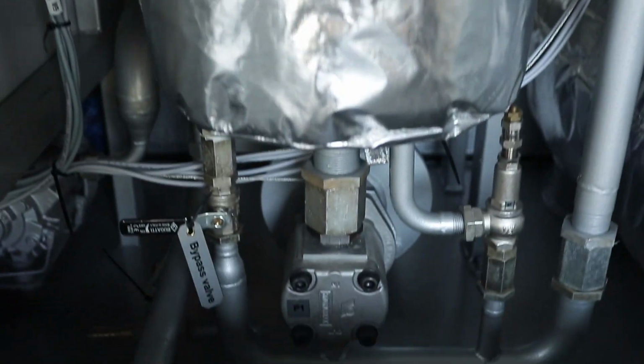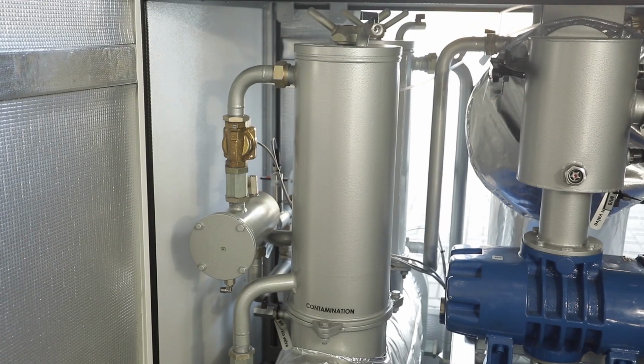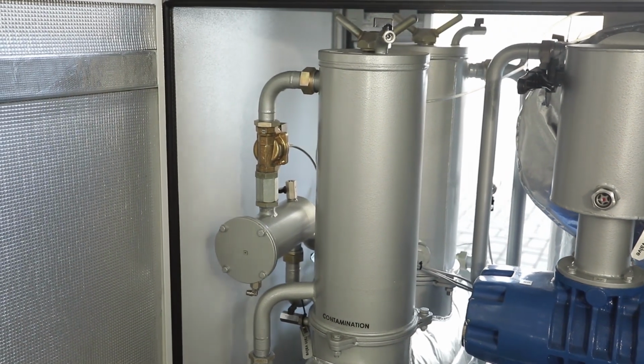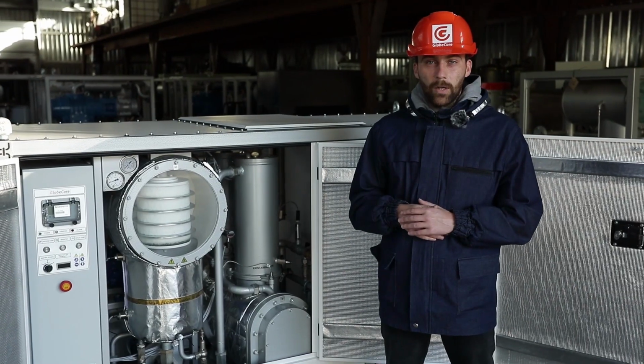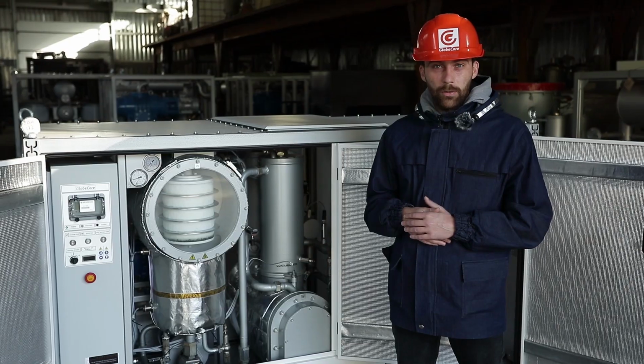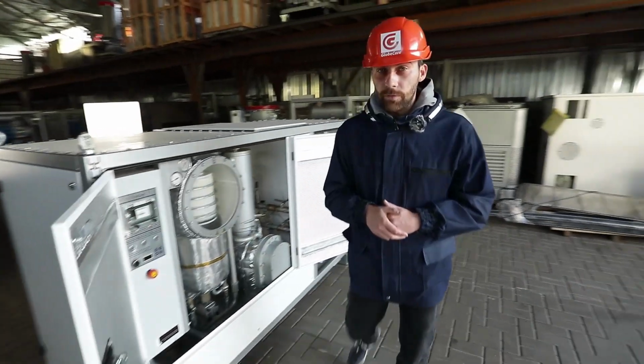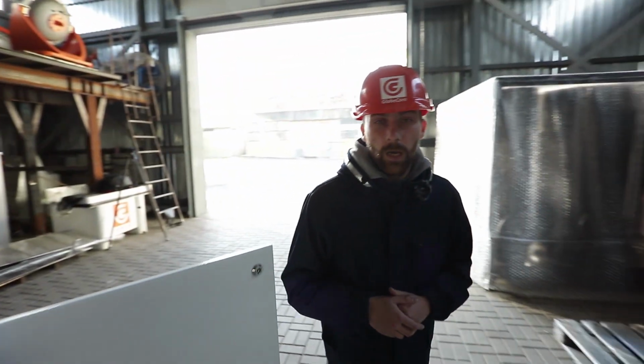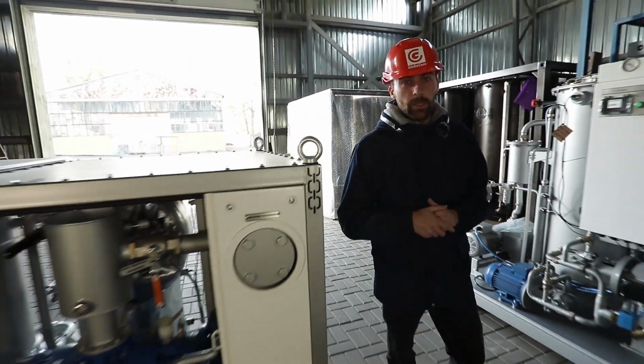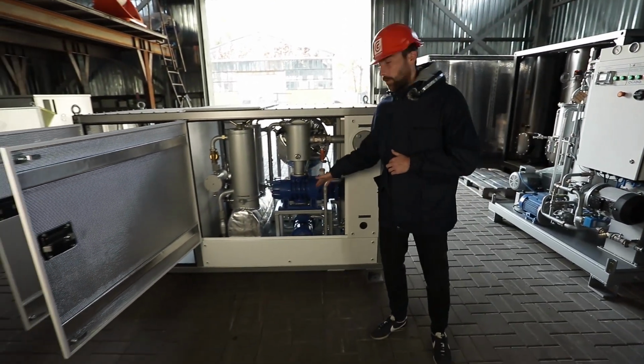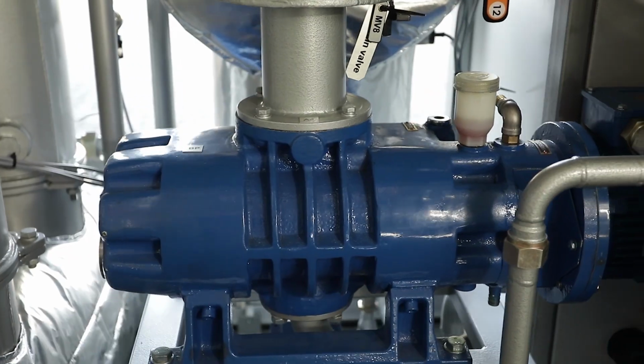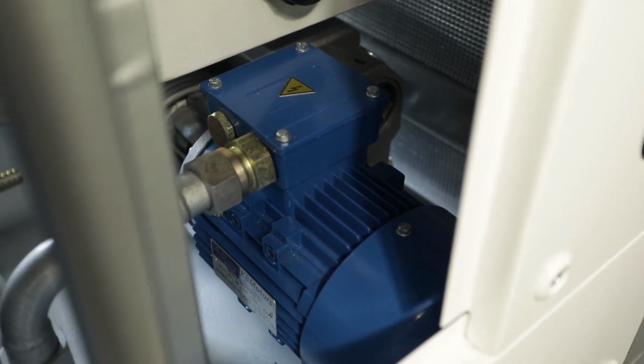Then, the dielectric liquid flows down the column, where it is pumped out and passes through another filter with a filtration fineness of 5 microns. At the unit outlet, the quality of dielectric liquid purification is compliant with Purity Class -14/12 of ISO 4406. Now, let's discuss the design features of the UVM-1 machine.